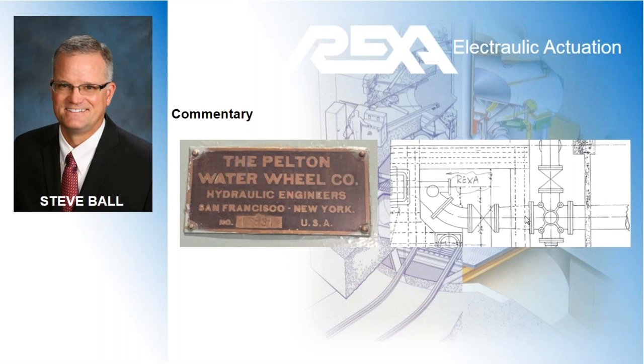Well, a single speed motor with a big bull gear and a lead screw obviously wouldn't satisfy that ability very easily, and it's not very concise or precise needle positioning. We came across the Rexa product and started to evaluate its ability to do set points, but also two-speed operation. So what we ultimately did was employ the Rexa servo and actuator system on the power needle, where the close speed was set for 15 seconds per inch, not to exceed, and that was within the design of that particular actuator, so it could not exceed that. The two-speed option is engaged only on the open. It's open call for open, and that would go up to almost 3 seconds per inch in opening.